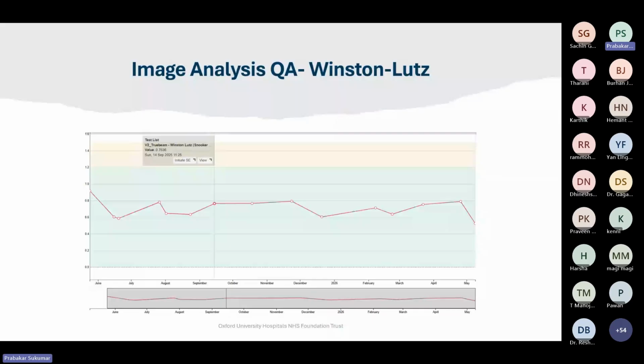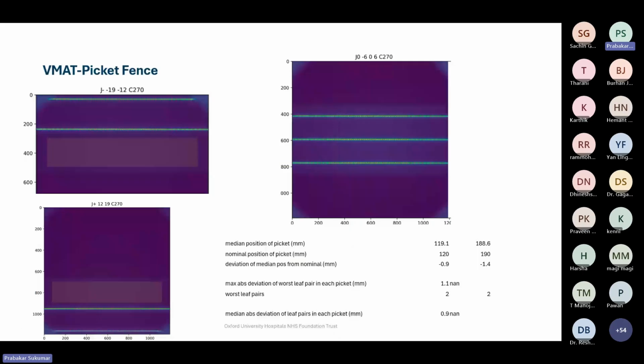The next test that we use is the picket fence test. This is one of the tests that has been created by one of the eminent physicists in our department. The picket fence test is performed for a single energy at different gantry angles to see the impact of gravity. They did different measurements, like distal and proximal MLCs for the Halcyons, because it is a dual layer MLC. And for the TrueBeams, we have done it on the A and B banks. First of all, they delivered it from the A bank. You can see minus 12 and minus 19 positions, and plus 12 and plus 19 for one of the jaws, and then different positions.